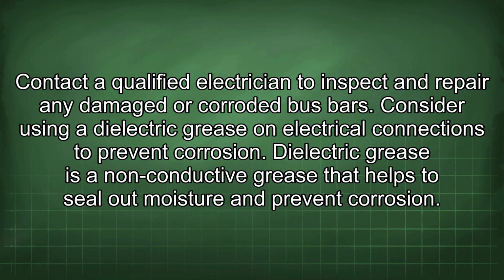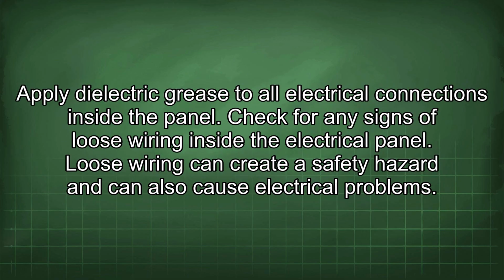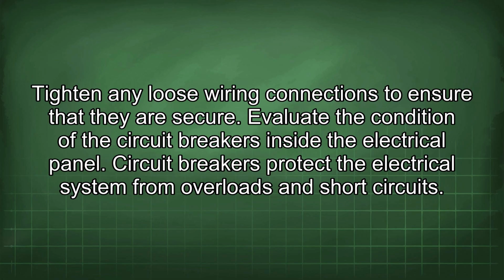Consider using a dielectric grease on electrical connections to prevent corrosion. Dielectric grease is a non-conductive grease that helps to seal out moisture and prevent corrosion. Apply dielectric grease to all electrical connections inside the panel. Check for any signs of loose wiring inside the electrical panel. Loose wiring can create a safety hazard and can also cause electrical problems. Tighten any loose wiring connections to ensure that they are secure.